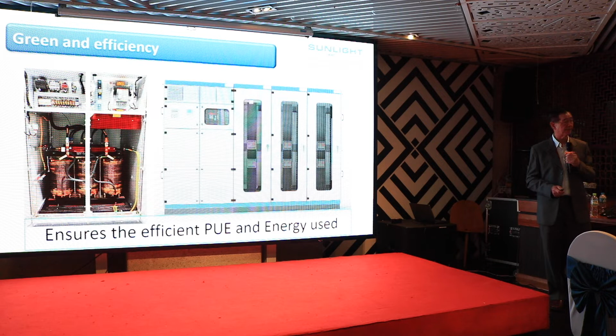An example of a data center that has a PUE of 1.33: if you look at the content, 75% is for the IT load, 12% mechanical, and 13% basically electrical. This is collected from one of the data centers that has a PUE of 1.32, and that's their breakdown composition. That means you really cut down a lot on the efficiency of your cooling.